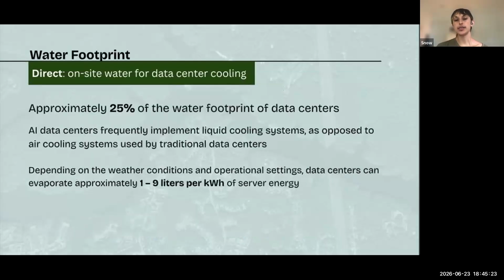Direct water footprint is the on-site water used for data center cooling, representing approximately 25% of the water footprint of data centers. AI data centers frequently implement liquid cooling systems as opposed to the air cooling systems traditionally used with traditional data centers. Depending on weather conditions and operational settings, data centers evaporate water at approximately 1 to 9 liters per kilowatt hour of server energy.